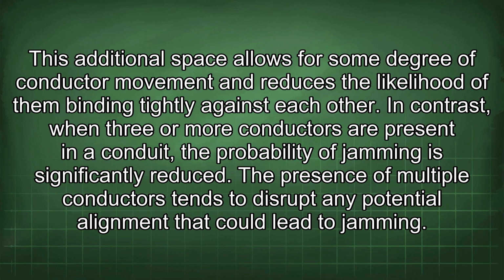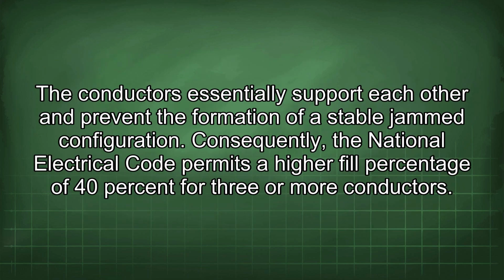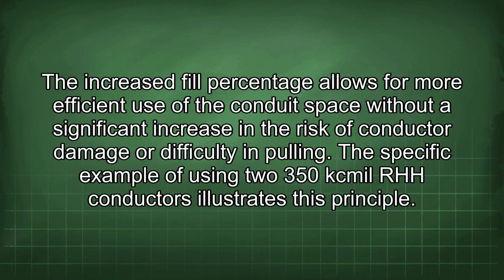This additional space allows for some degree of conductor movement and reduces the likelihood of them binding tightly against each other. In contrast, when 3 or more conductors are present in a conduit, the probability of jamming is significantly reduced. The presence of multiple conductors tends to disrupt any potential alignment that could lead to jamming. The conductors essentially support each other and prevent the formation of a stable jammed configuration. Consequently, the National Electrical Code permits a higher fill percentage of 40% for 3 or more conductors. The increased fill percentage allows for more efficient use of the conduit space without a significant increase in the risk of conductor damage or difficulty in pulling.